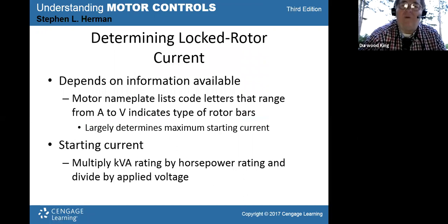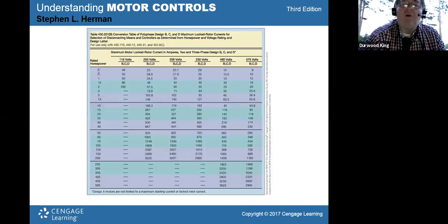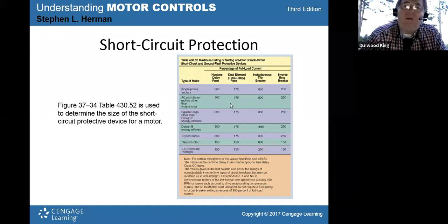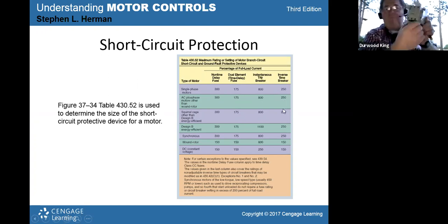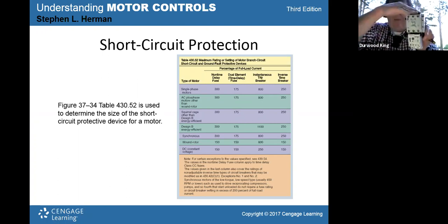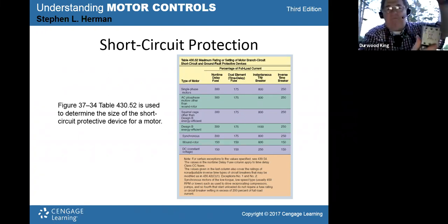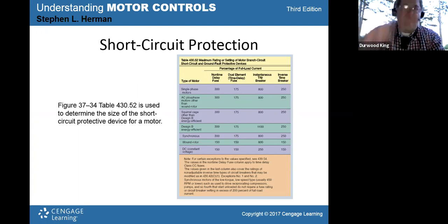We've already looked at locked rotor. We've already looked at how to calculate that. Those are charts that already calculate for you what it is, if you had to know. What this chart tells you is about your fuses or your breakers that are upstream from above. Okay, you got your starter right here, right? So here's your starter. Now, what's feeding the starter would be some fuses or a breaker feeding into the starter. So that's where this chart comes in. What's your protection above the starter? All you got to deal with from motors is going to be this here, fellas. You're going to be in that column there with time delay fuses for motors. Motors are going to use time delay dual element fuses. That's your percent right there.